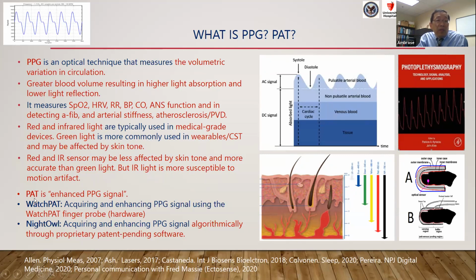Now, what is PAT? What is the PAT signal? In fact, the PAT signal is an enhanced PPG signal. Traditionally, every time we talk about the PAT signal, we think of WatchPAT. But WatchPAT really acquires and enhances the PPG signal through their finger probe. There's a finger probe with a hard shell, and inside there's a pneumatic cuff. After you stick your finger in, this cuff provides a constant pressure throughout and avoids venous pooling, so that it gives us a very good PPG signal. This is what PAT is.